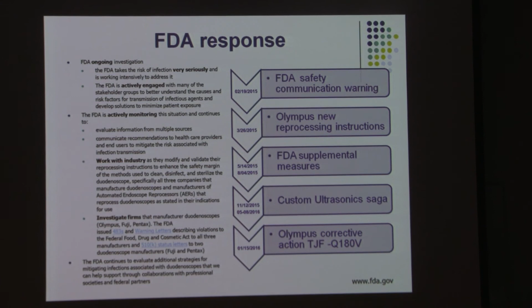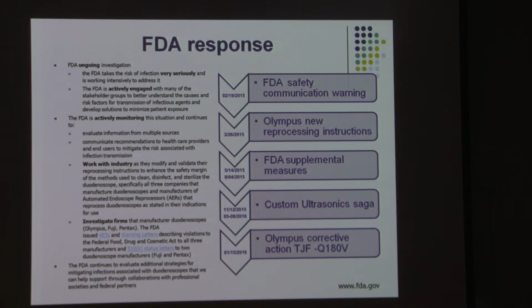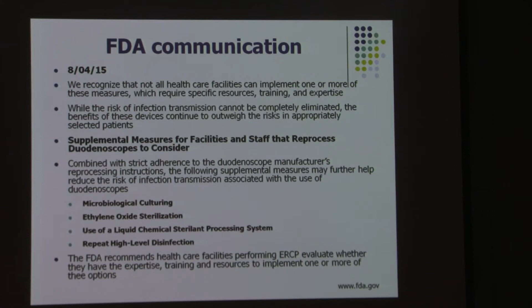As a response to those outbreaks, FDA came out with several recommendations as well as communication warnings, worked extensively with the industry, and ordered the manufacturers to undergo several additional studies. As a result of that work, this is one of the major FDA communications from August of 2015, where, combined with strict adherence to duodenoscope manufacturer processing instructions, the following supplemental measures were suggested, and that includes microbiological culturing, gas sterilization, use of a liquid chemical sterilant processing system, or repeat high-level disinfection. And FDA encouraged healthcare facilities to implement one or more of those options.